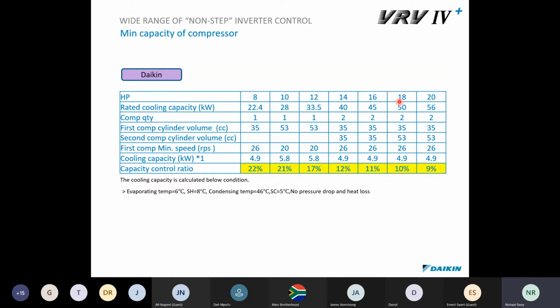When you're designing, for example, a hotel or an office block, and you have a machine in a storeroom or a room, the amount of charge in your total system must not exceed a percentage of the volume. I think it's 400 grams per square, if I'm not mistaken, in the room area. Oh, sorry, 400 grams per cubic meter.